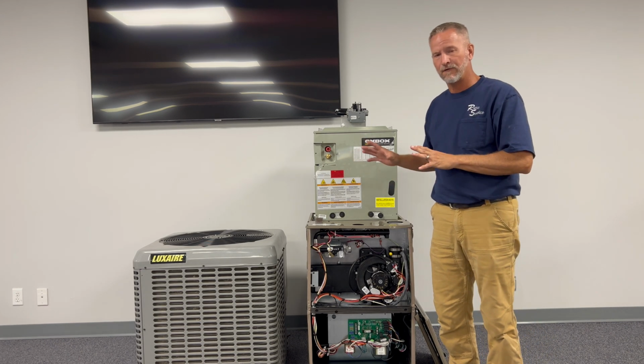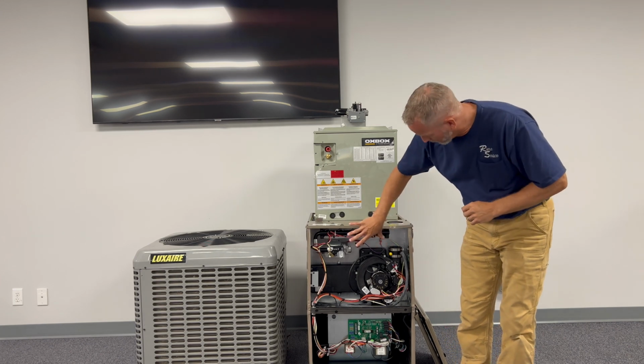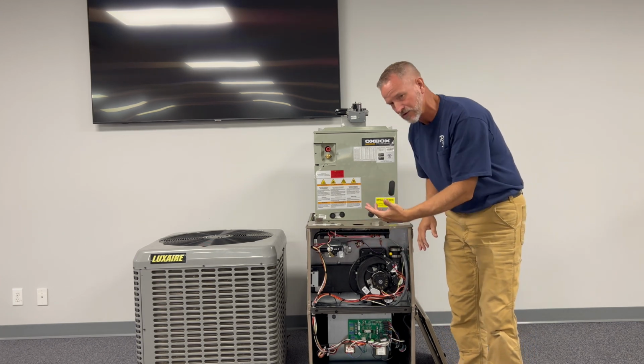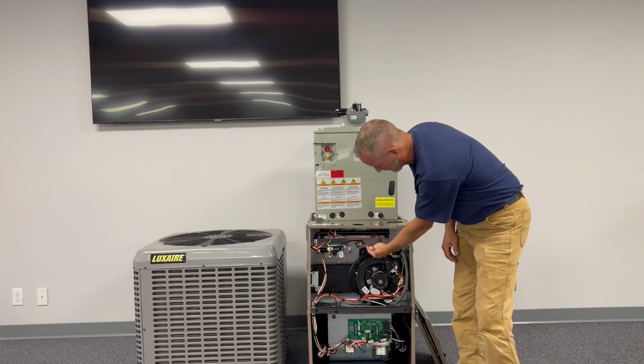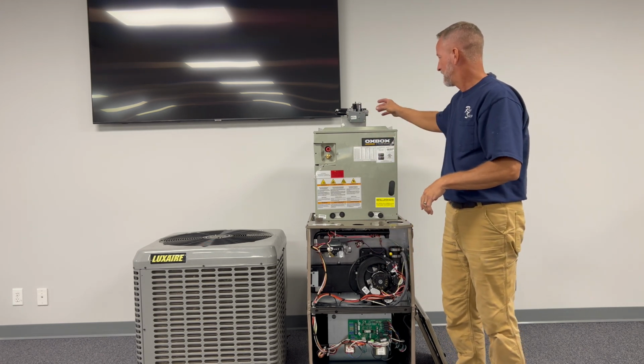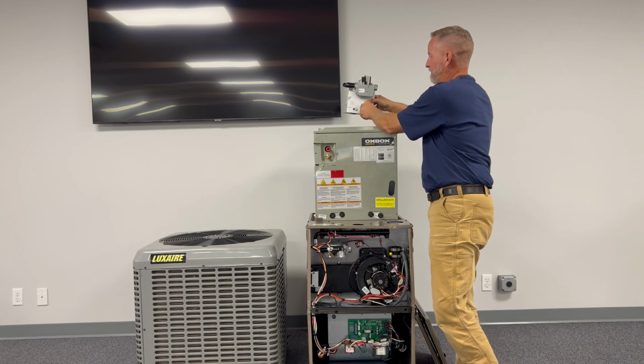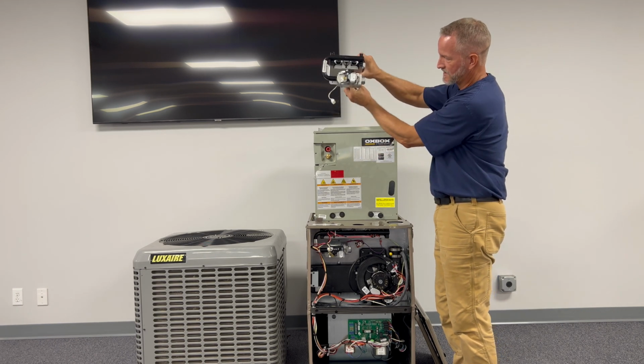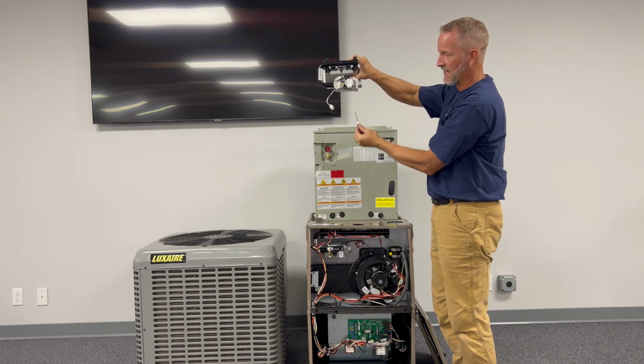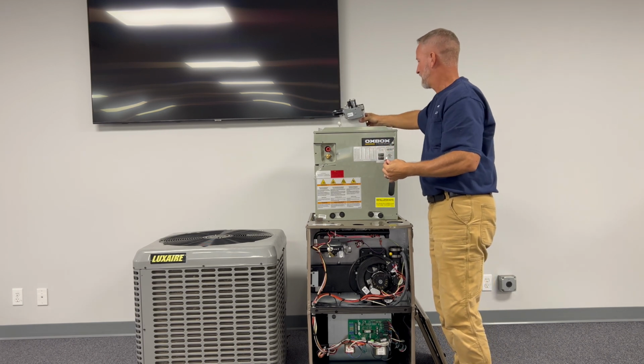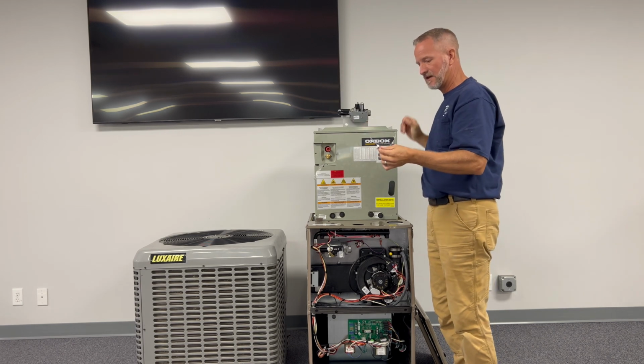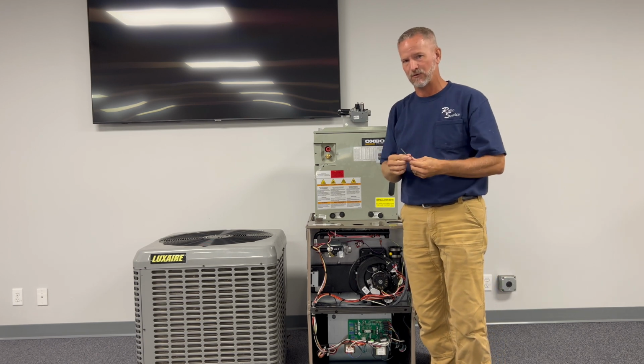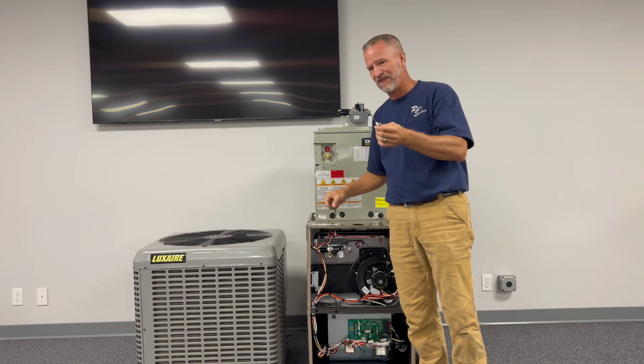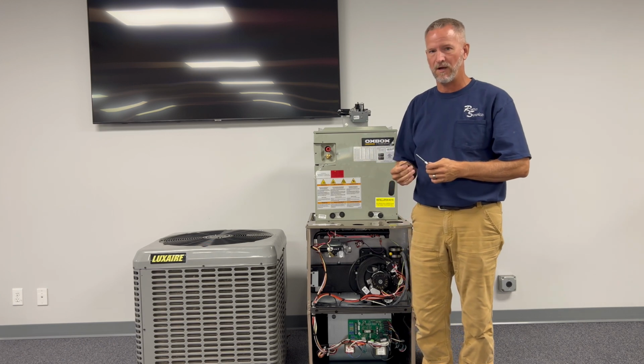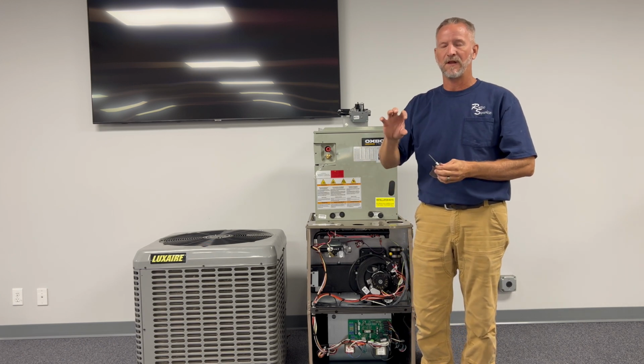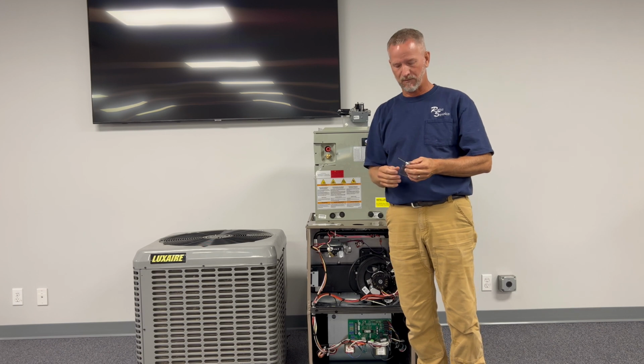Secondly, we have our flame sensors. In our combustion chamber, our flame sensors come in contact with the flame from the bottom of the heat exchanger. Now, this is a smaller example of that, and we can see that that flame sensor simply attaches from the bottom. Now, this flame sensor, because it sits in the airflow and has a flame in contact with it, sometimes it gets a film on it, and then it doesn't tell the furnace to run. We can usually identify that by a flame coming on and then shutting off within a couple of seconds.